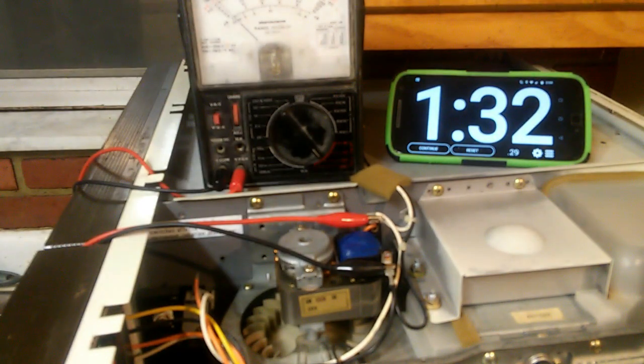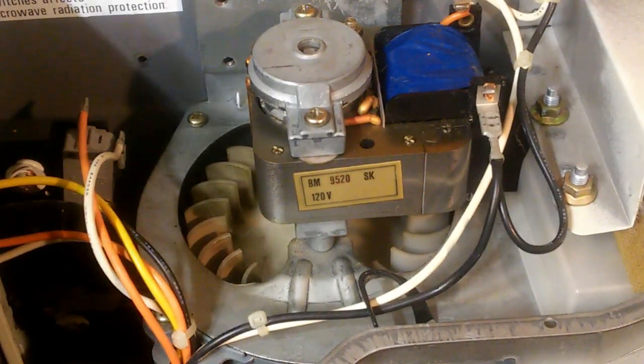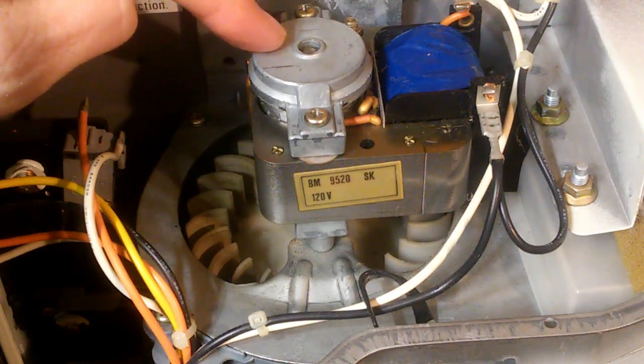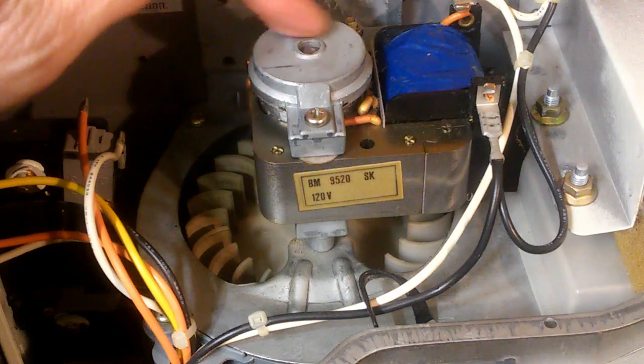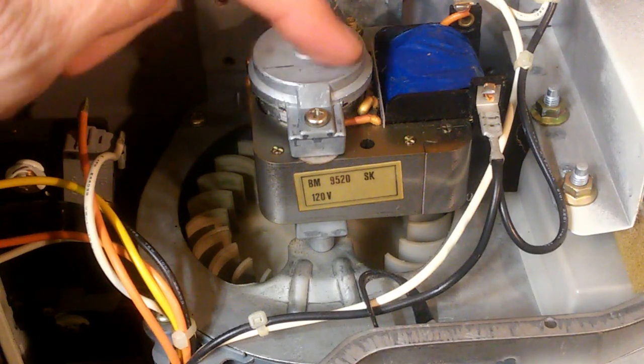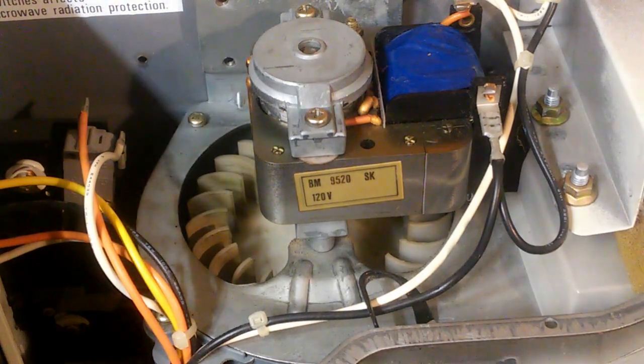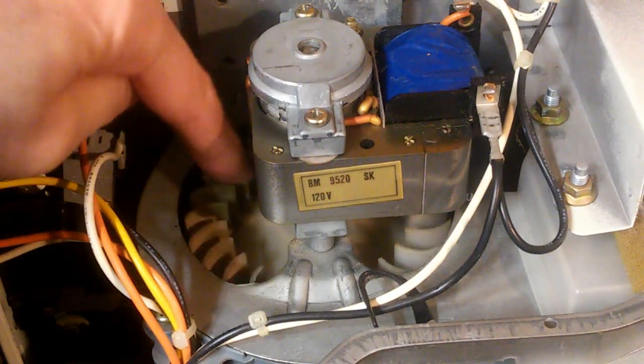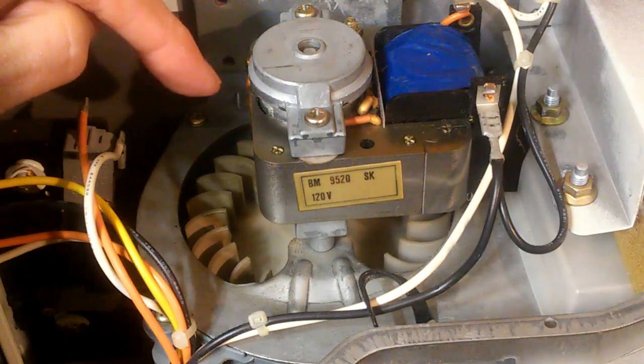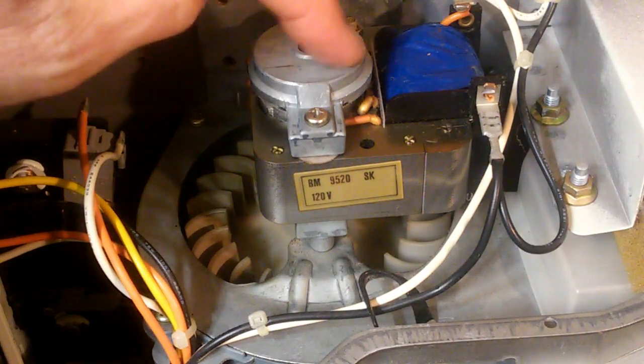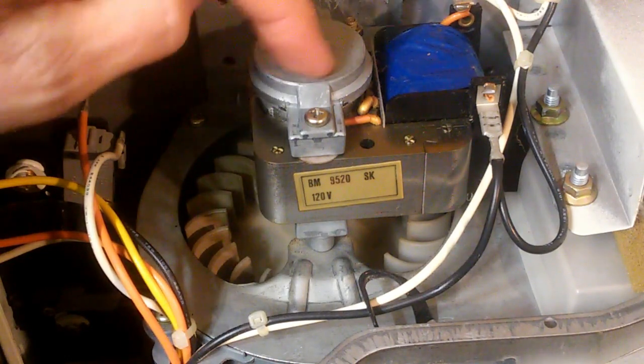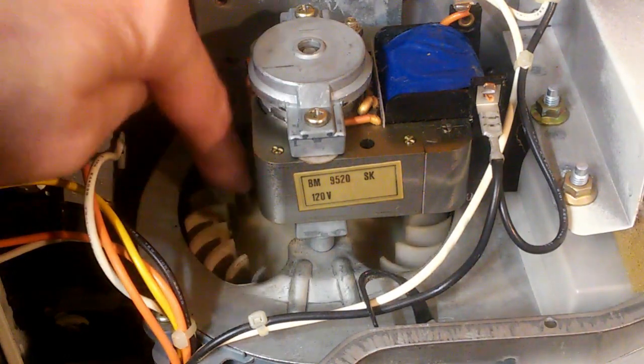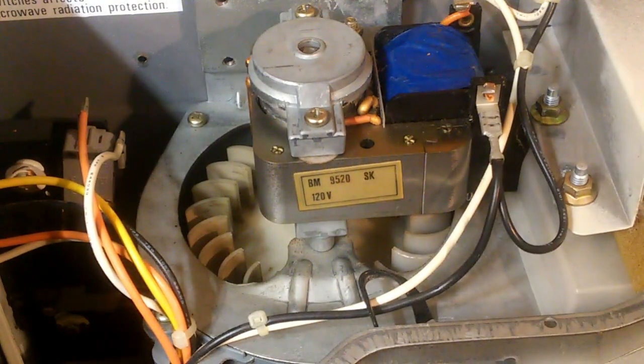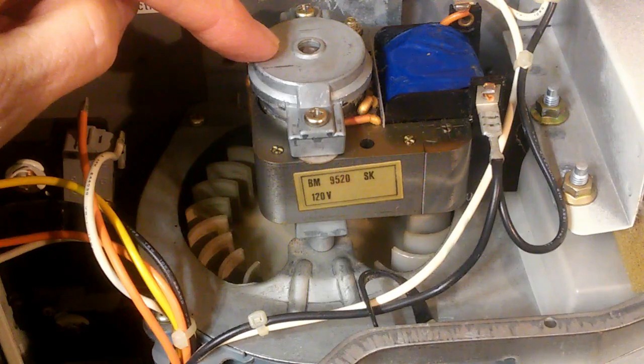We are applying a continuous voltage of 120 volts, so voltage is not the problem. The problem appears to be something mechanical in the fan. My guess is that the lubricant inside these bearings is too thick, perhaps dried out over time or accumulated dirt, giving the fan too much resistance. As it spins it will heat up in the bearings, the lubricant will become a little more liquid, and eventually the fan will be able to turn at full speed. So that's my guess: something wrong with the bearings or the lubricant in them.